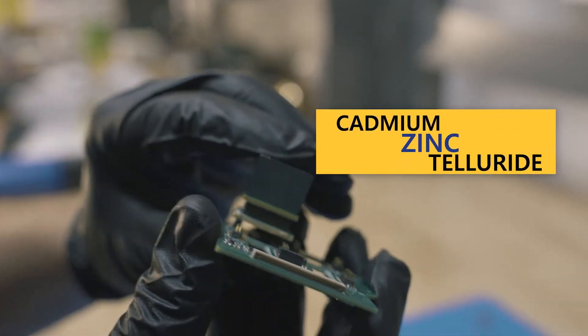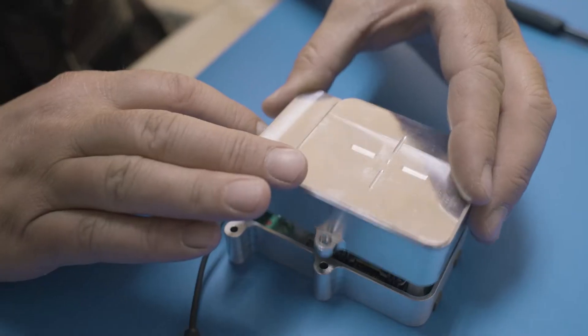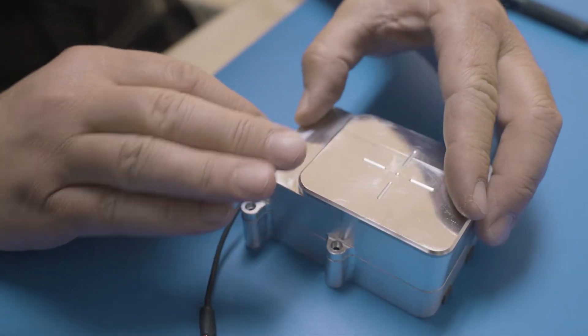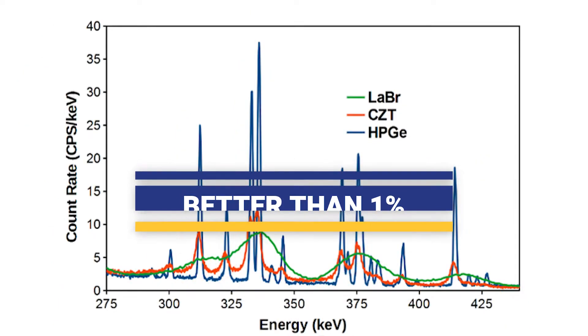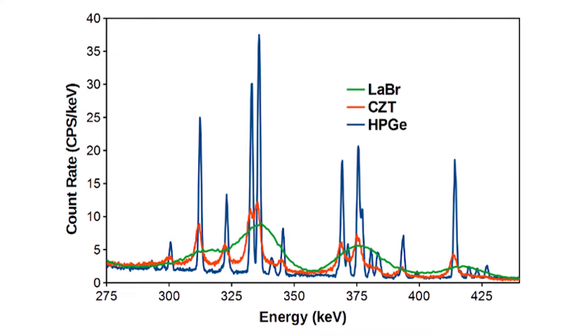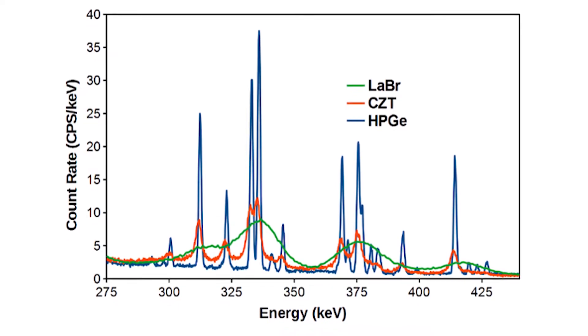CZT stands for Cadmium Zinc Telluride, a semiconductor material that does not need to be cryogenically cooled to detect radiation. A major advantage of our technology platform is our energy resolution for gamma ray spectroscopy. We get better than 1% full width half max at 662 keV, which puts us well beyond the capability of your typical field spectrometer like a sodium iodide detector or lanthanum bromide type device.